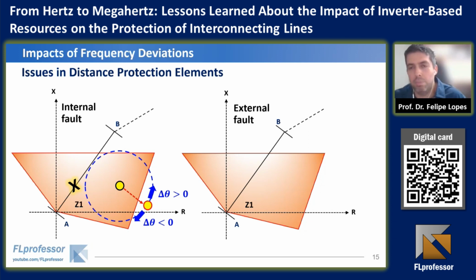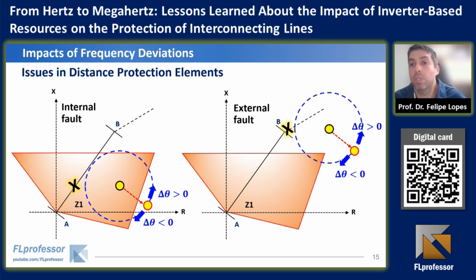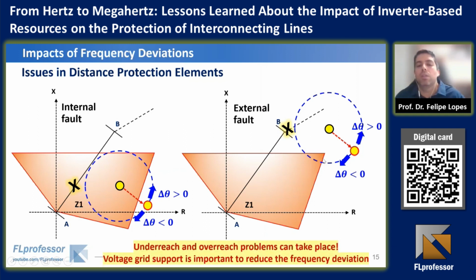It's interesting, but in the case of external fault, the impedance is supposed to take place here. It is moved toward the right side, and if our rotating characteristic takes place, we start with a correct operation, but if this impedance travels here, it can enter the operating characteristic, so the protection can present a malfunction. So it is difficult to predict. So underreach and overreach problems can take place.